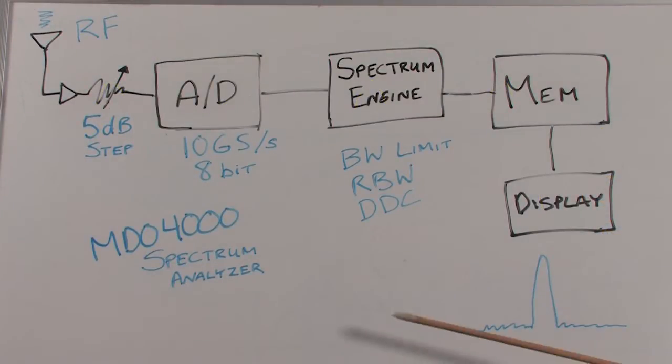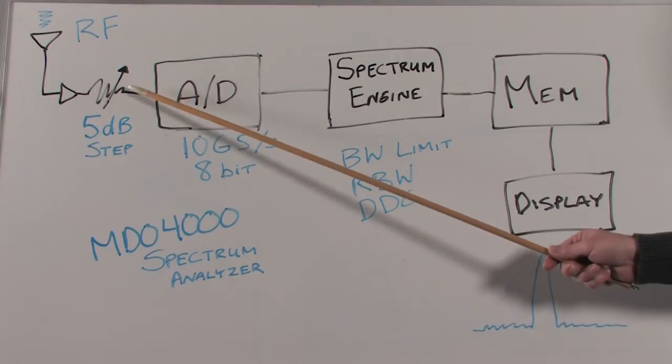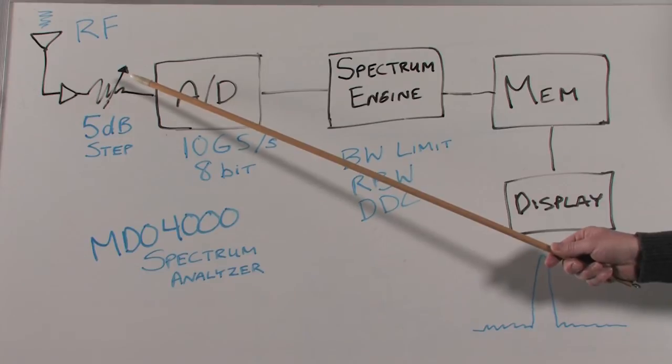Now take a look at the block diagram for the integrated spectrum analyzer in the MDO. Like other spectrum analyzers, there is an input amplifier and step attenuator specifically optimized for RF measurements.